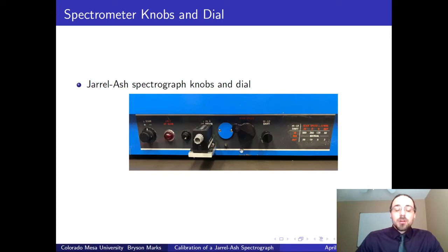And on the middle right here we have the scan speed knob. Now this scan speed knob is attached to the transmission and enables you to change between 4 different speed settings of the high-low shift function. And that's where this high-low shift function knob is. And you can pull that in, you can pull that out or have it pushed in to change between high or low.